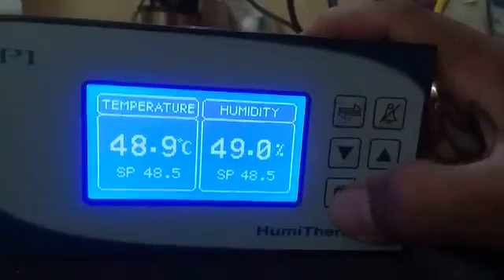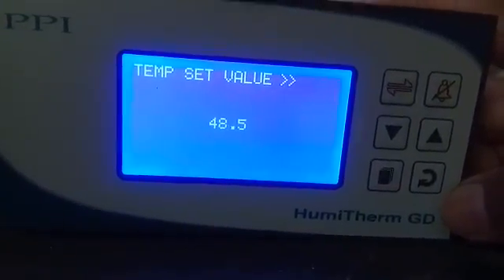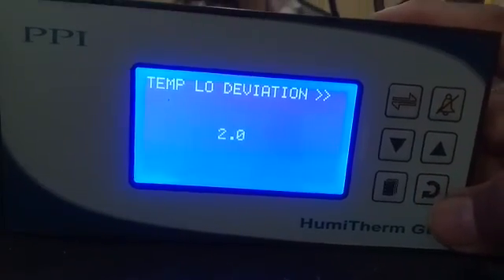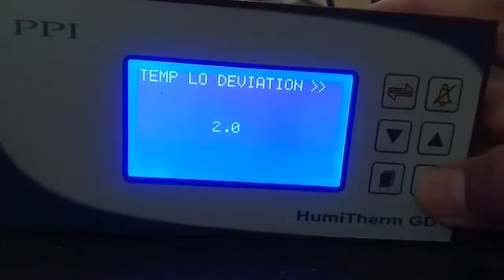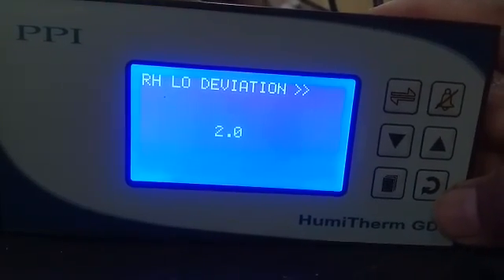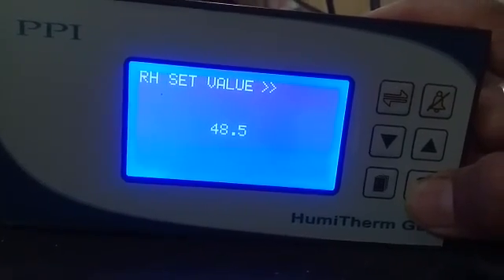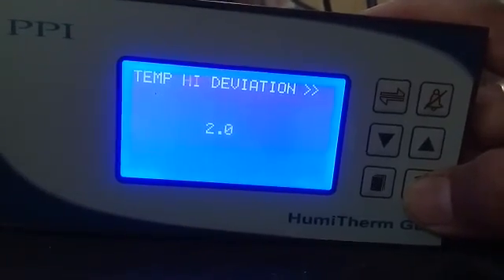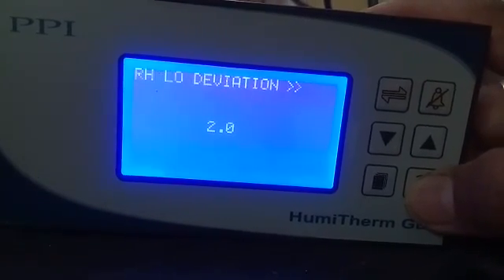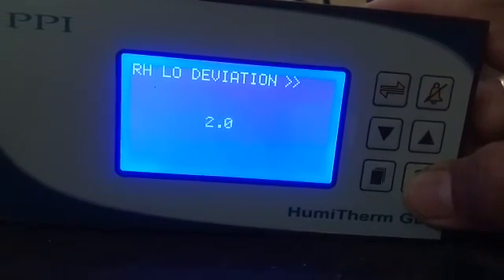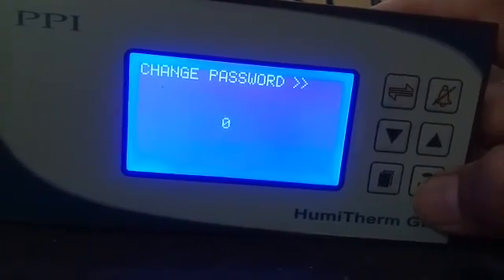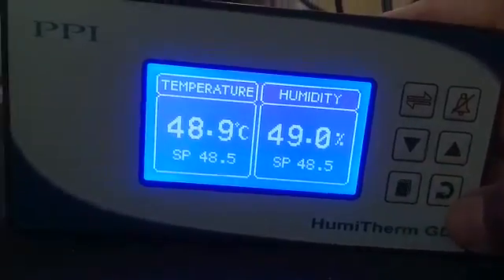If you press the page button, you can see the enter password option in the temperature set value. These are the operator parameters: temperature set value, temperature RS set value, temperature low deviation, temperature high deviation, RH low deviation, RH high deviation, and change password — if you want to change the password, you can change it here.